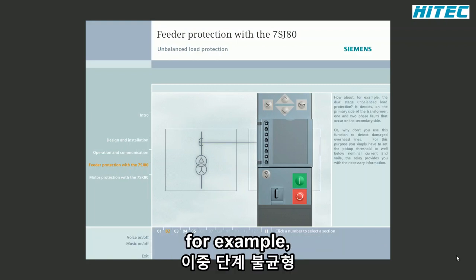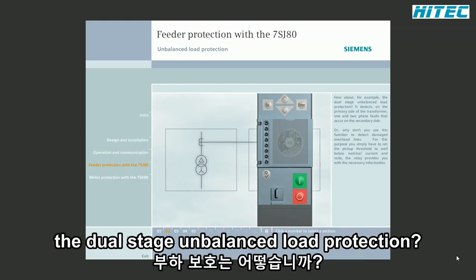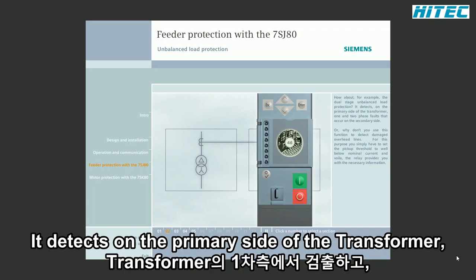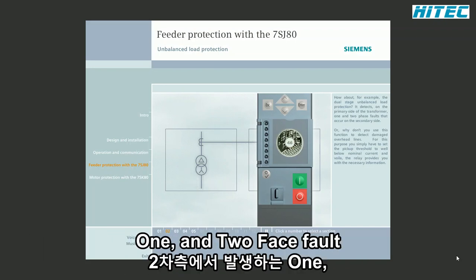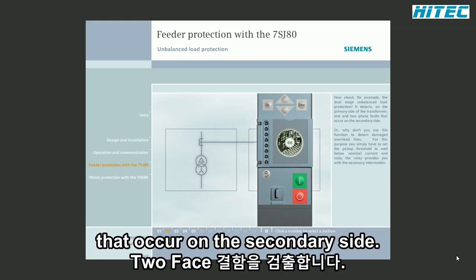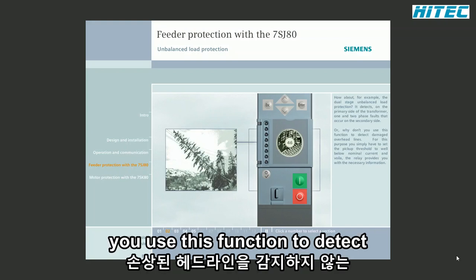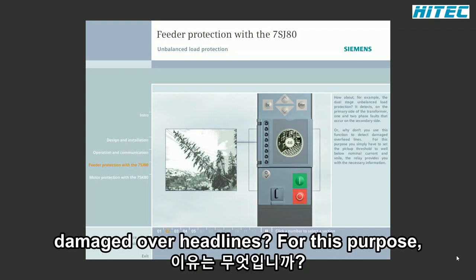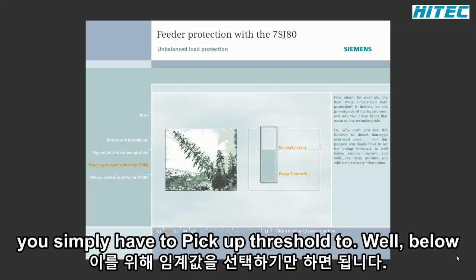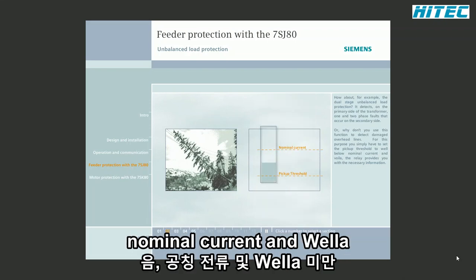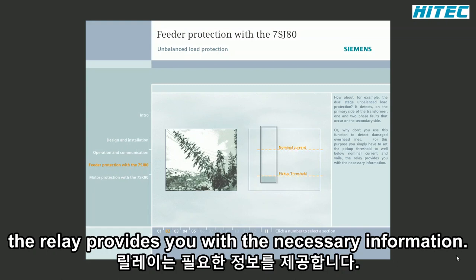How about, for example, the dual-stage unbalanced load protection? It detects on the primary side of the transformer 1- and 2-phase faults that occur on the secondary side. Or why don't you use this function to detect damaged overhead lines? For this purpose, you simply have to set the pickup threshold to well below nominal current, and voila, the relay provides you with the necessary information.